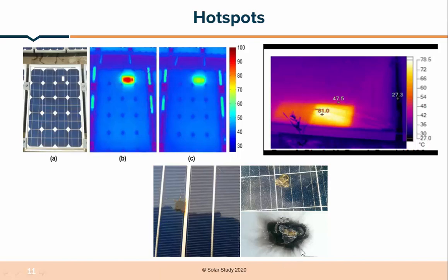You can also see burning in the solar module. This is due to high infrared rays. Or this may also happen when we have an older module; at that time we get this kind of corrosion and burning effect. These are some of the hotspots as well as defects in the module.